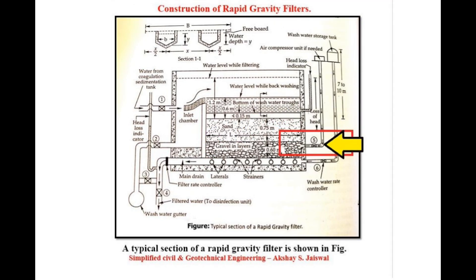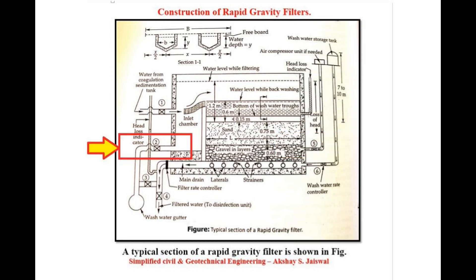Valve number 5 is closed after supplying the required amount of air. Compressed air pass hone ke baad valve number 5 ko band kiya jata hai. The dirty water resulting from washings overflows into the wash water trough and is removed by opening valve number 2 through the inlet chamber into the wash water gutter. The process of washing the filters and removing the dirty water is generally continued for a period of 3 to 5 minutes. Washing ke baad nikalne wala mela paani wash water trough mein laaya jata hai aur valve number 2 se inlet chamber se hote hue wash water gutter se bahar nikaala jata hai.